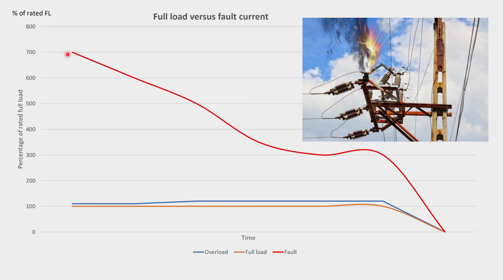A fault tends to be a very low impedance path, like somebody took the output of that inverter and just shorted the leads out together. Somebody took the leads of the battery and just touched them together. That is a fault. Whereas an overload is like putting too many appliances on. So you had one floodlight, you added another floodlight, and now you added your laptop. That's overloading it. But the current does not look like that. It more looks like that.